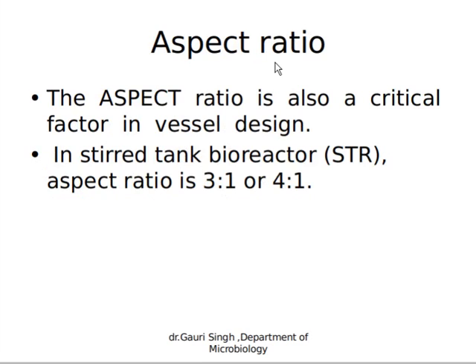For designing a fermenter, there is another important aspect, that is the aspect ratio of the fermenter. Aspect ratio is also a critical factor in designing a fermenter. Aspect ratio means height to diameter ratio. It varies between different types of fermenter. Generally, in a stirred tank fermenter or stirred tank bioreactor, the aspect ratio is 3:1 or 4:1, height to diameter. While in the case of a tower fermenter, the aspect ratio should be 6:1.